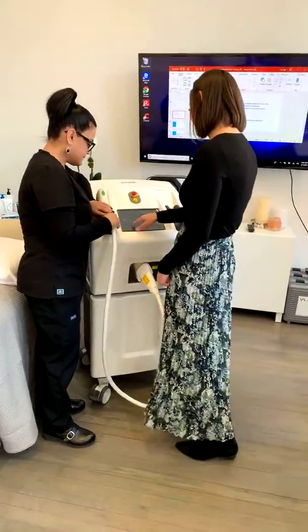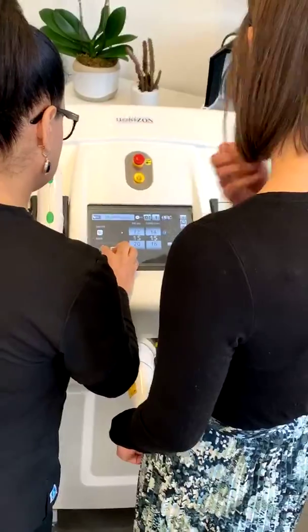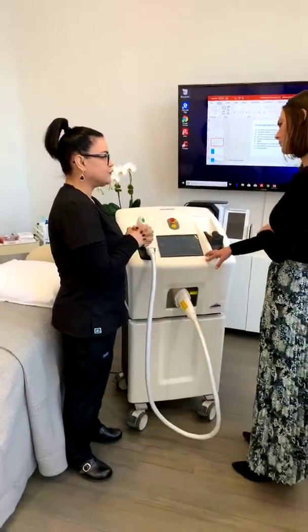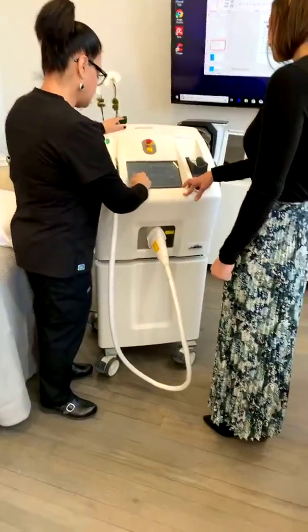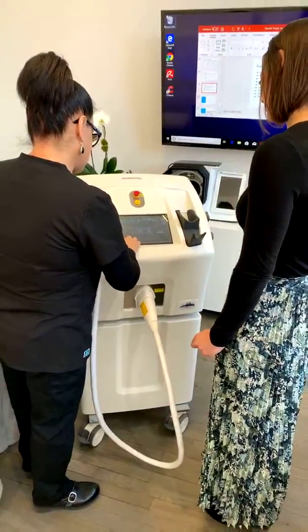So if you were doing dark pigmented, well, how would these be different? So right now, I changed it, it'll be 15-15. Some you're going to find it's not even going to move. I believe with hair removal it doesn't really drastically change. But when you're dealing with the different skin types, you can see some might move, some might not, because some of them are so close in range, they're not going to be much of a difference. It's going to want to do vascular light. It's also 6 by 15. Vascular dark.